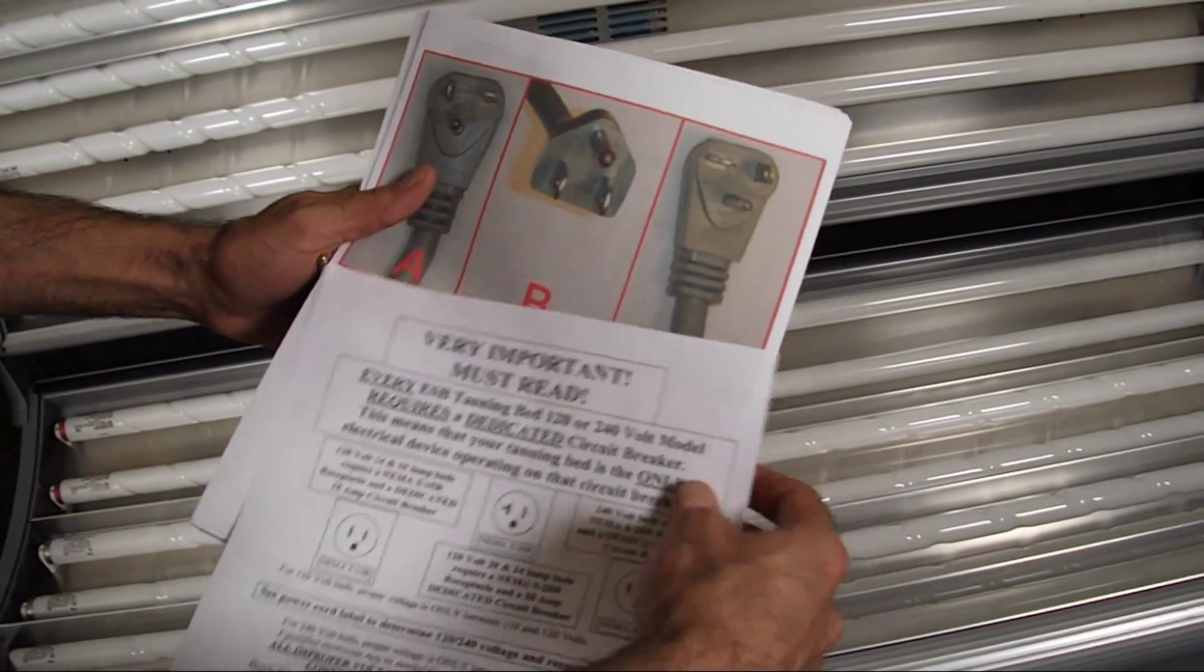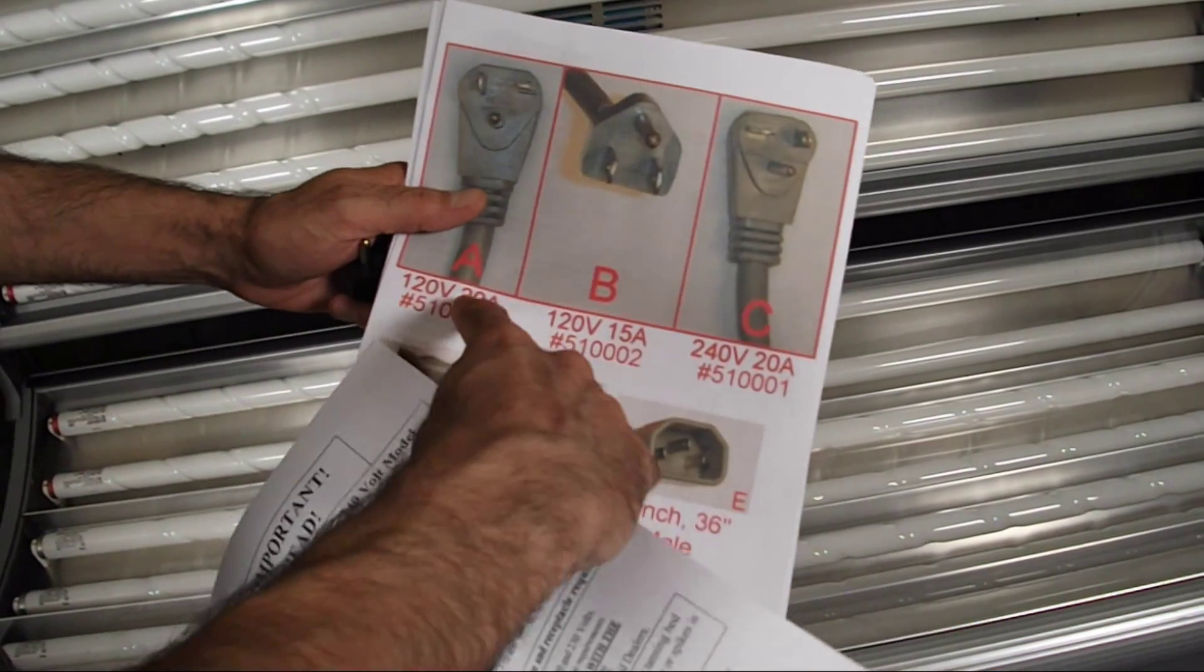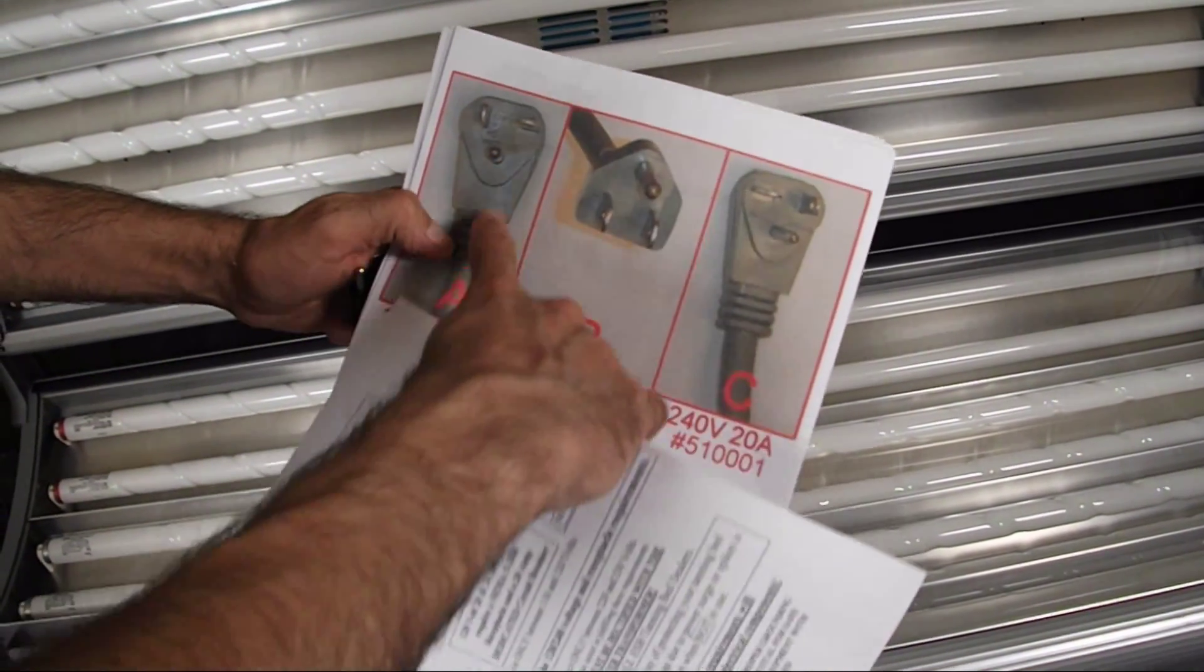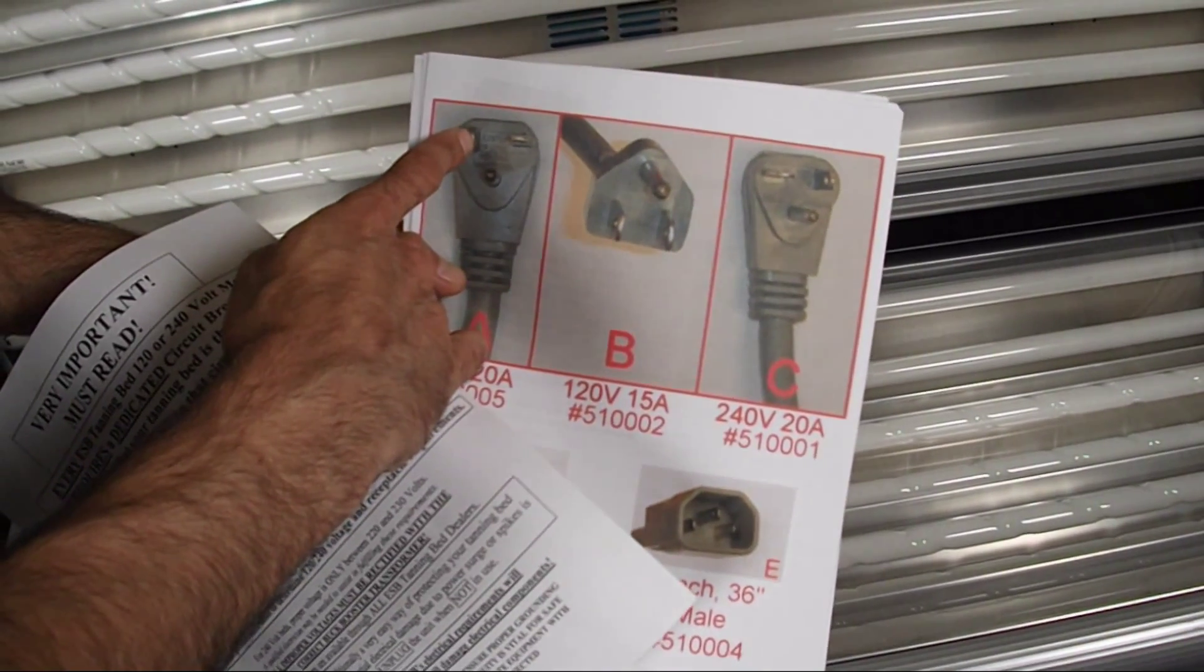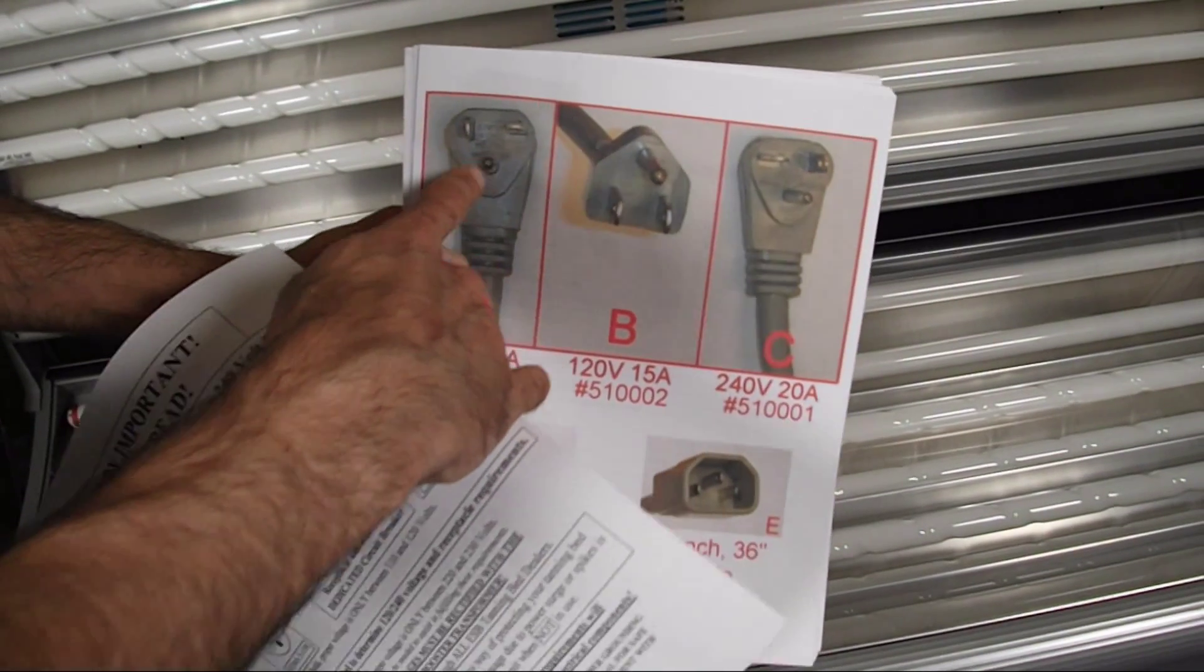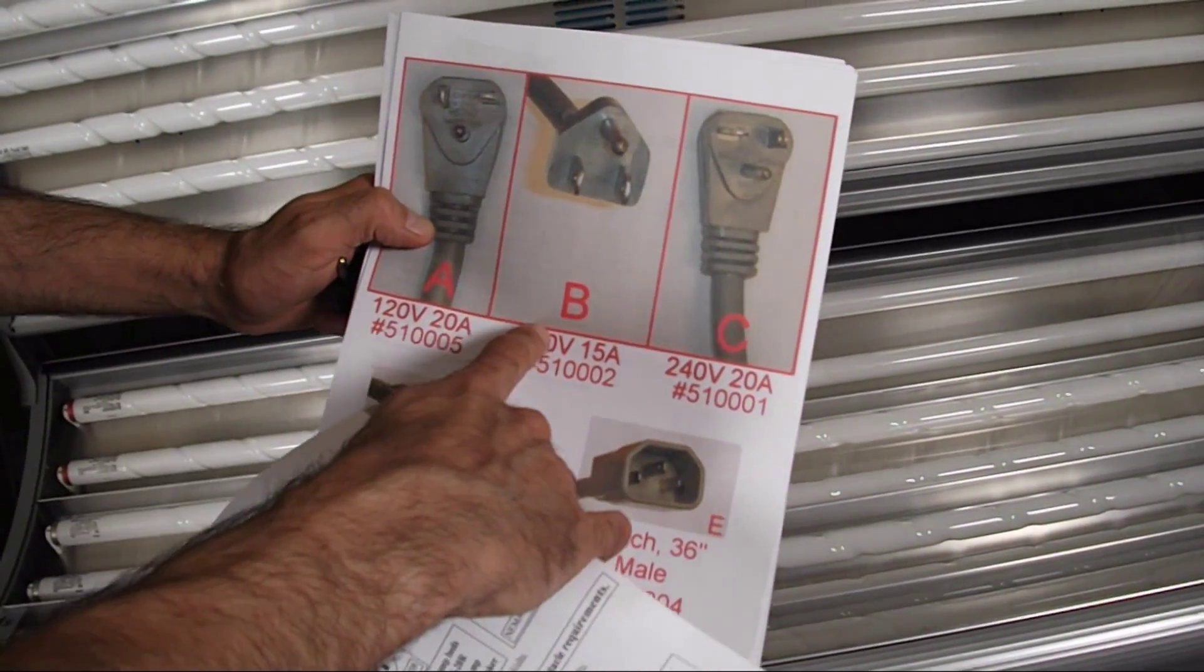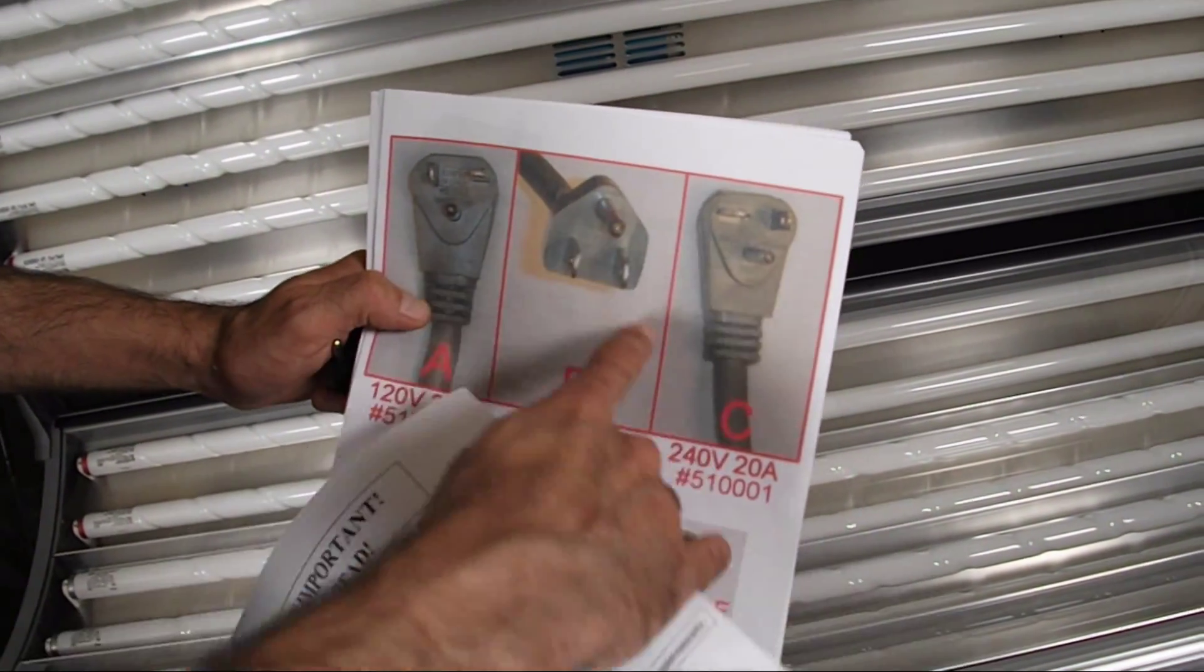These are what they look like here in this diagram, these first two. This is a 120 volt, 20 amp plug where you have a vertical terminal on the left and a horizontal on the right when the ground, the round one, is pointing right towards you. And this is the typical 15 amp plug with the two parallel blades.